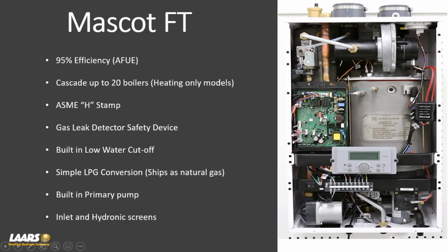If it's a clear condensate trap or you have a neutralizer out in the system, you should be looking at that. Why? Because if that's dirty, where's that coming from? It's coming from the heat exchanger. It's an immediate indication that you may want to open up that chamber and clean it if needed.